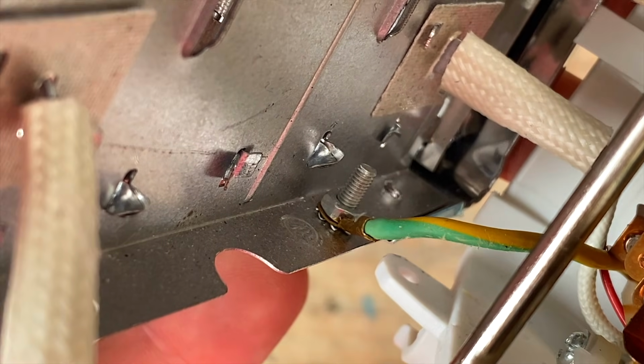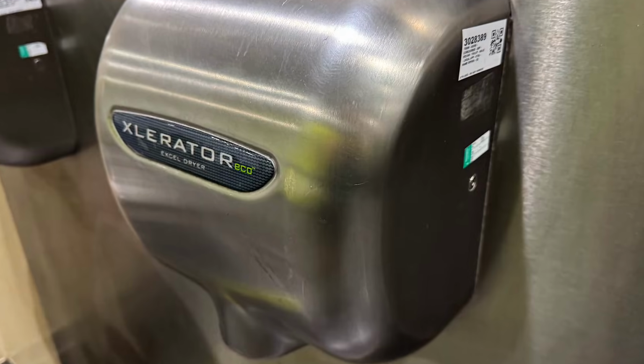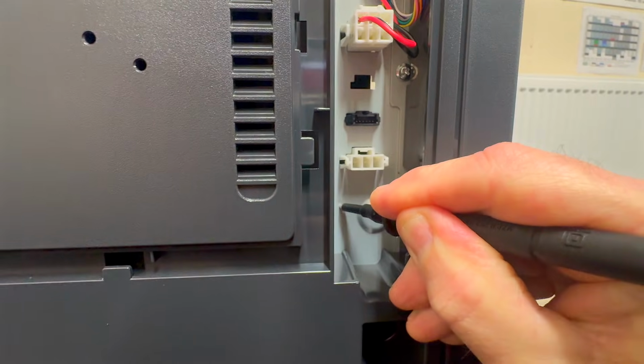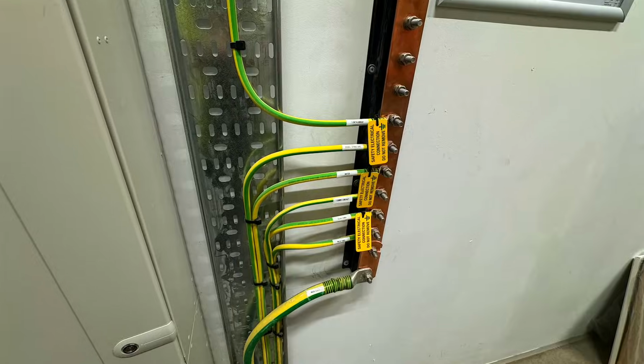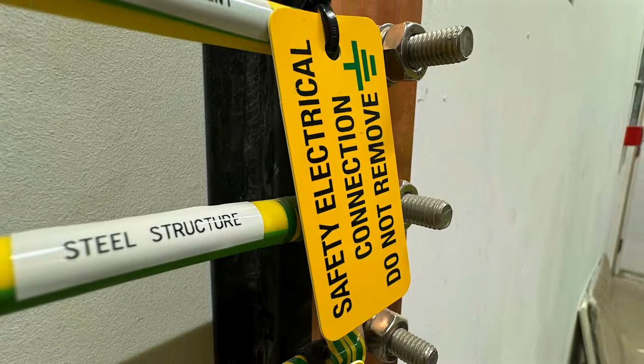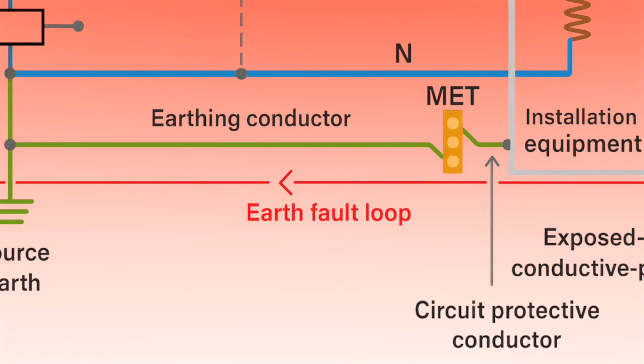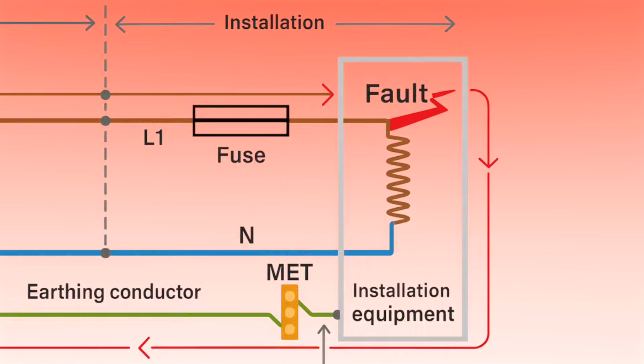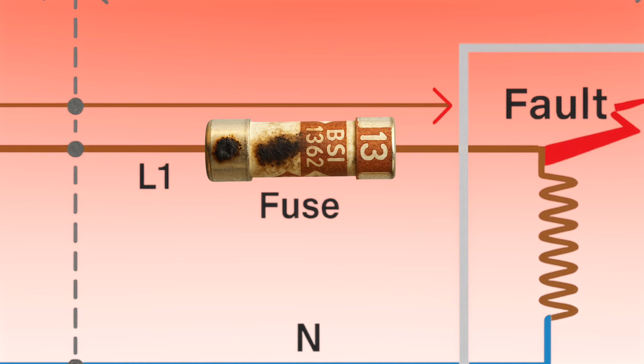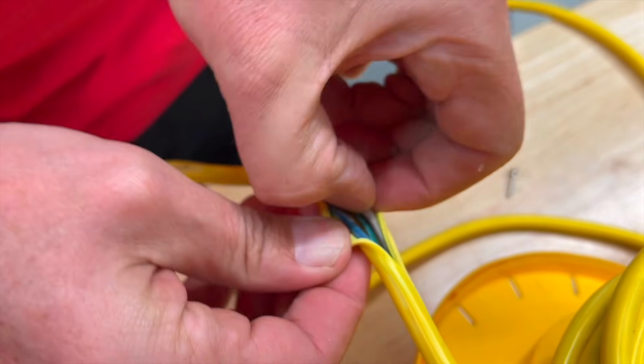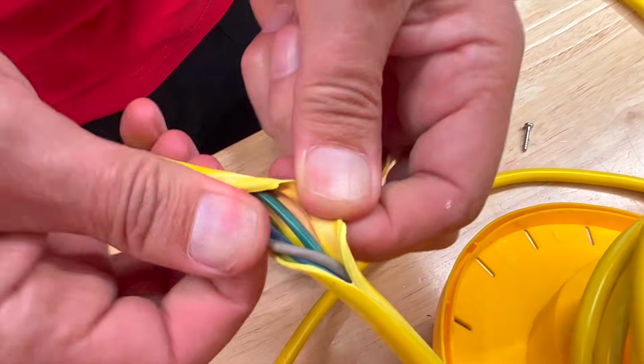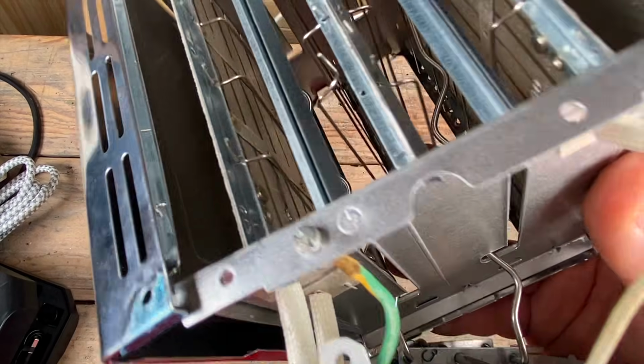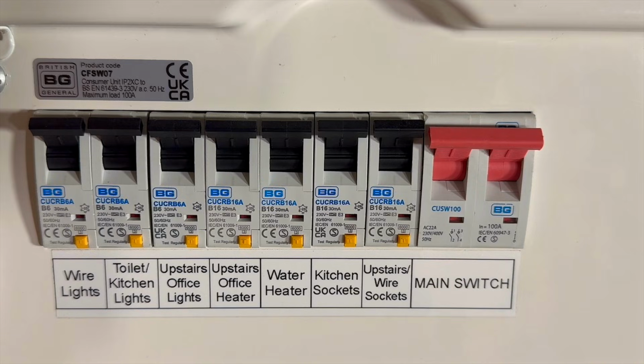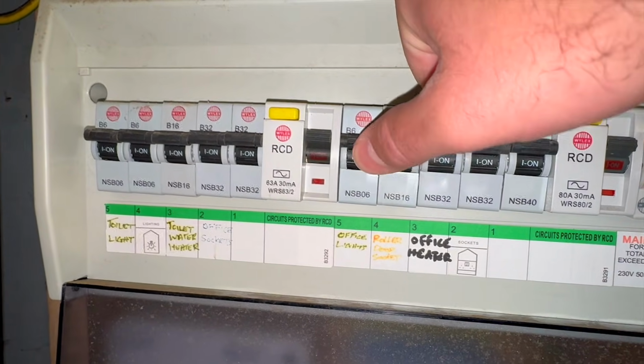Class 1 equipment uses exposed metalwork as part of the safety system, and that metalwork must be connected to earth. This is the same protective measure used throughout electrical installations, known as automatic disconnection of supply, or put simply, will blow the fuse or trip if something goes wrong electrically. If the basic insulation fails and a live conductor touches the metal casing, a fault current flows down that protective conductor. That current must be high enough to operate the fuse, circuit breaker, or RCD quickly. Once it trips, the fault is cleared and the danger is removed.